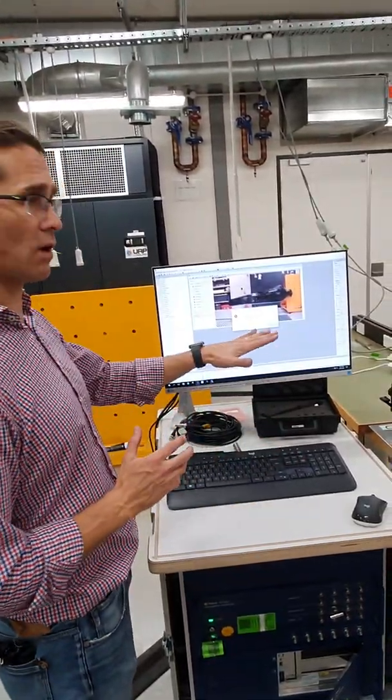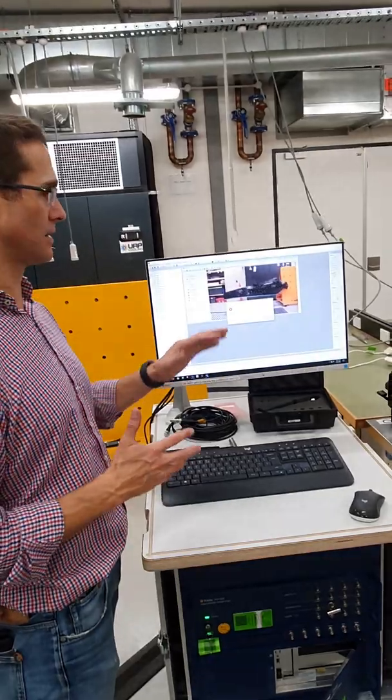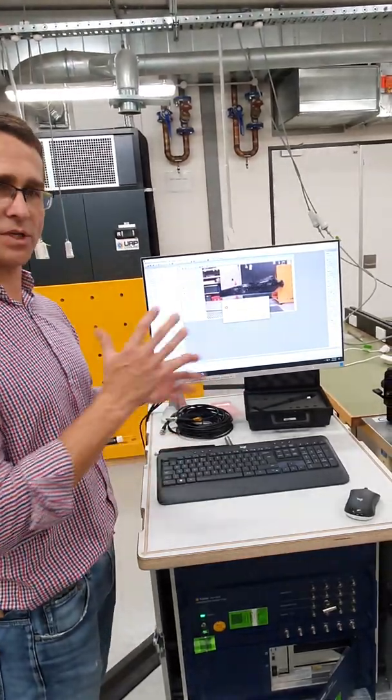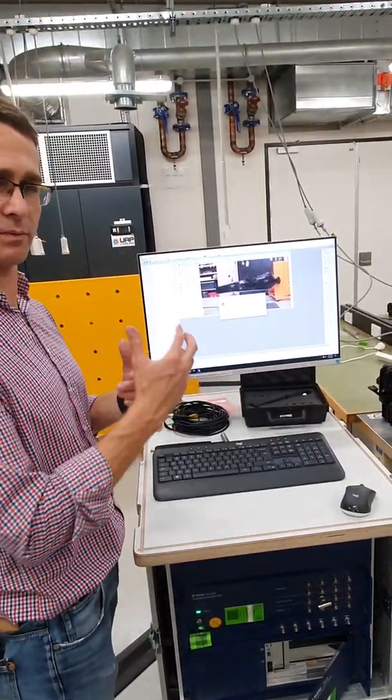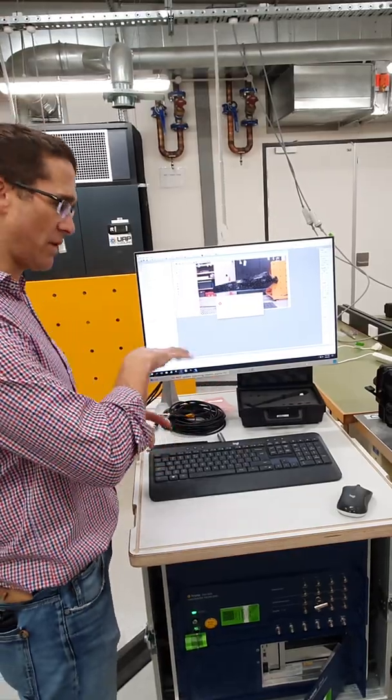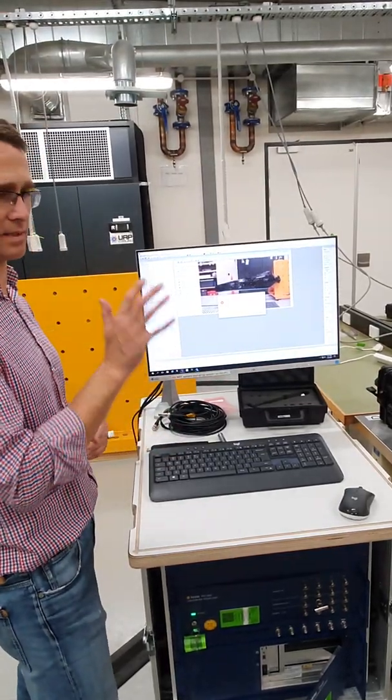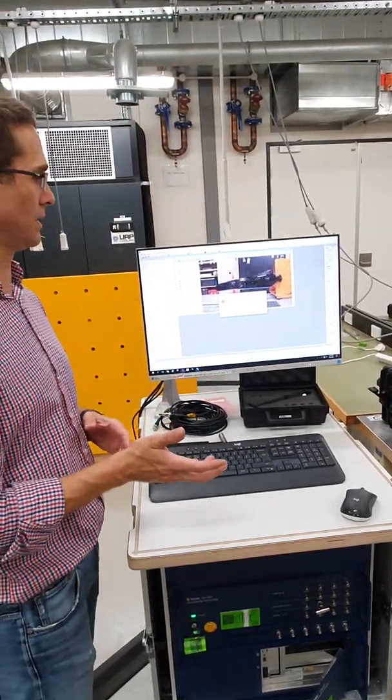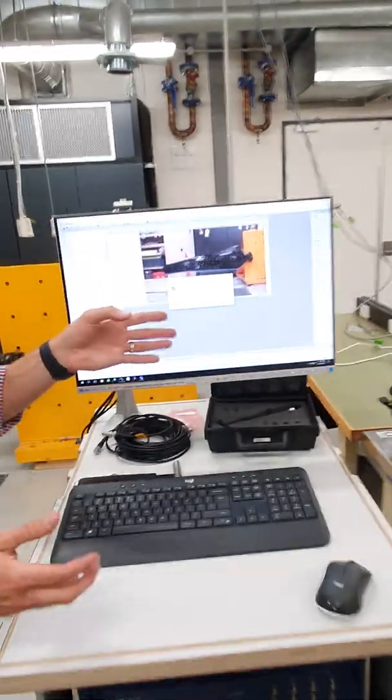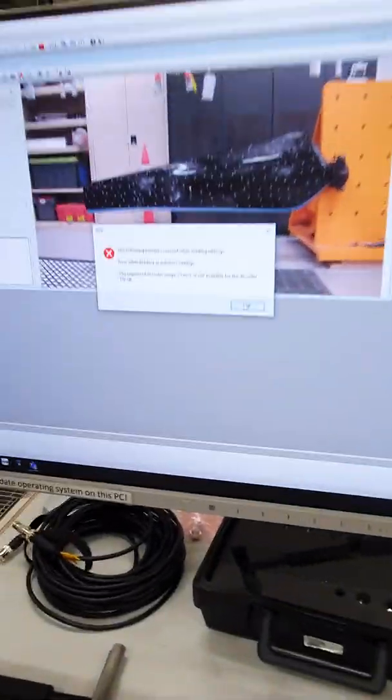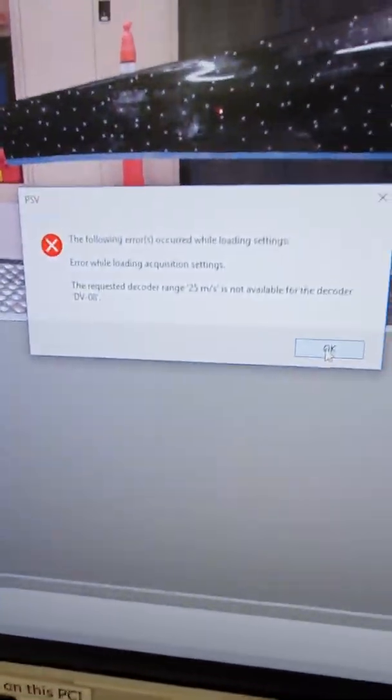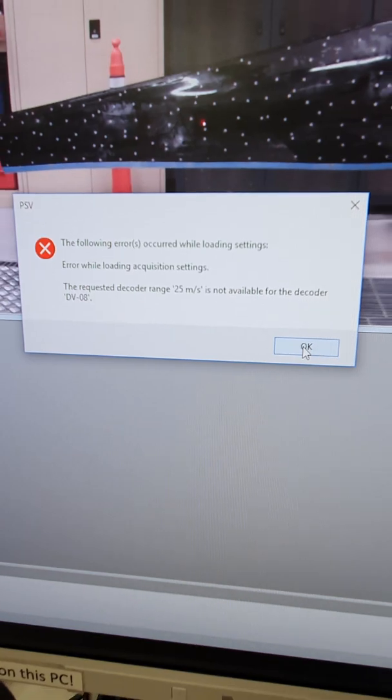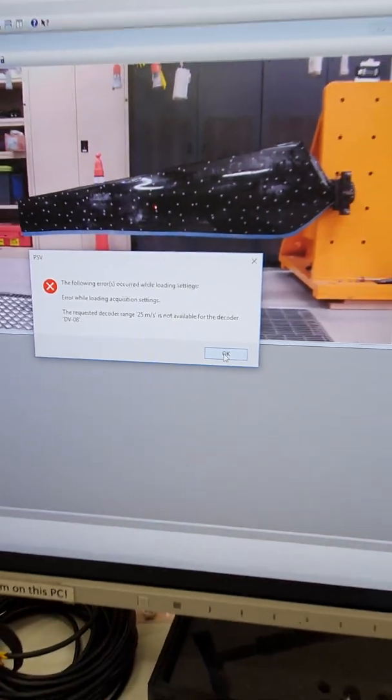So the software is telling us that I'm changing or I'm updating because previously we had a, we were using a different configuration. Previously we had the extra head connected, this time we've got the helium neon head. So you might get that error message depending upon which head was previously connected to the PSV500.